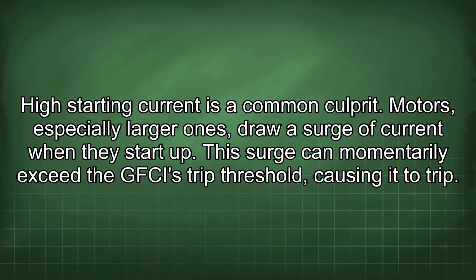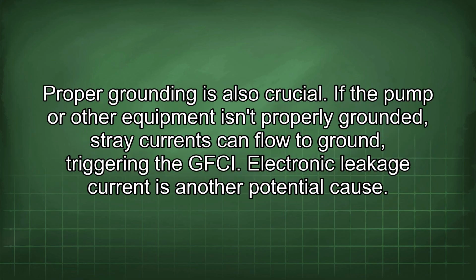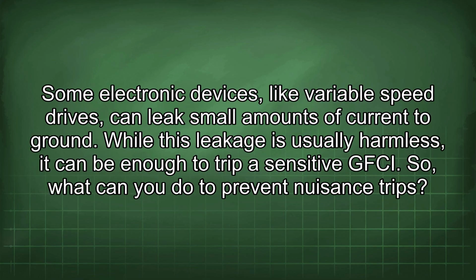High starting current is a common culprit. Motors, especially larger ones, draw a surge of current when they start up. This surge can momentarily exceed the GFCI's trip threshold, causing it to trip. Proper grounding is also crucial. If the pump or other equipment isn't properly grounded, stray currents can flow to ground, triggering the GFCI. Electronic leakage current is another potential cause. Some electronic devices, like variable speed drives, can leak small amounts of current to ground. While this leakage is usually harmless, it can be enough to trip a sensitive GFCI.